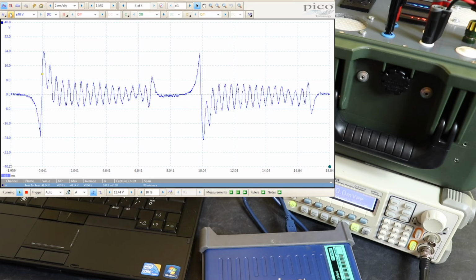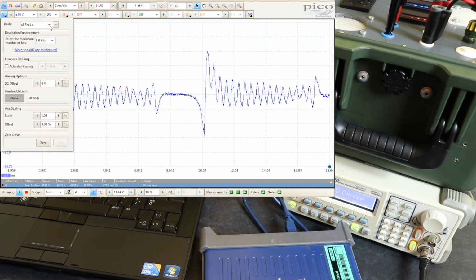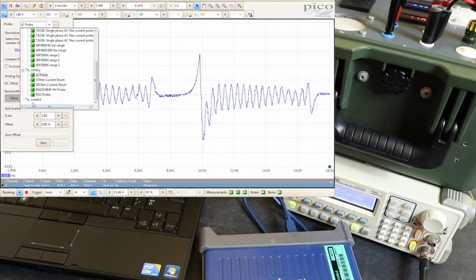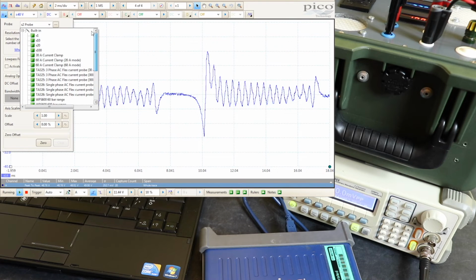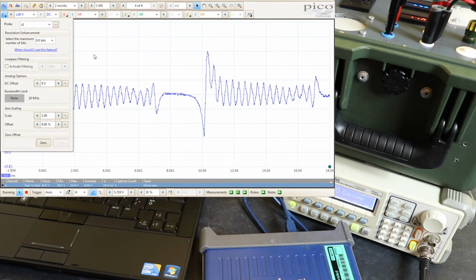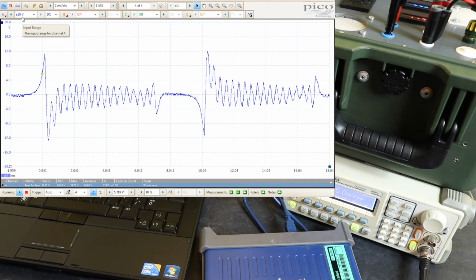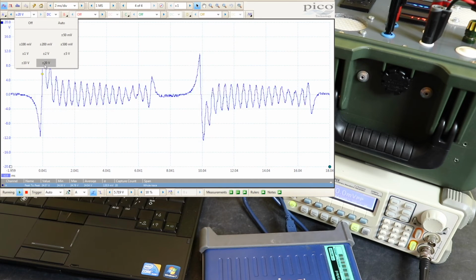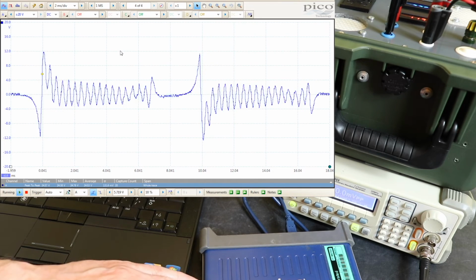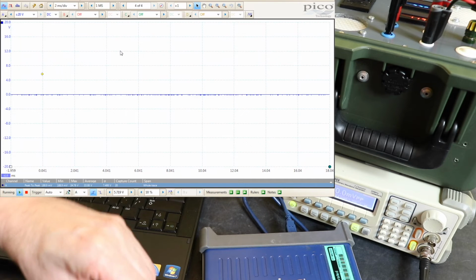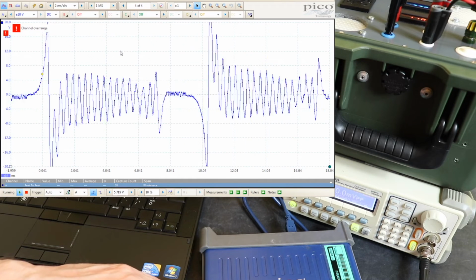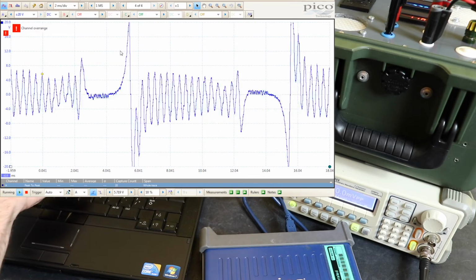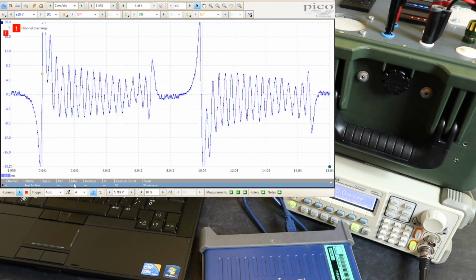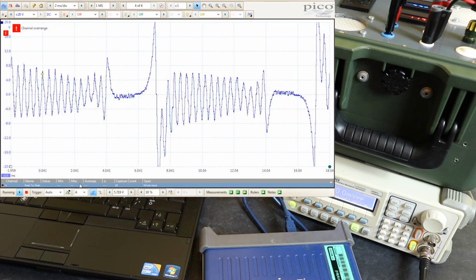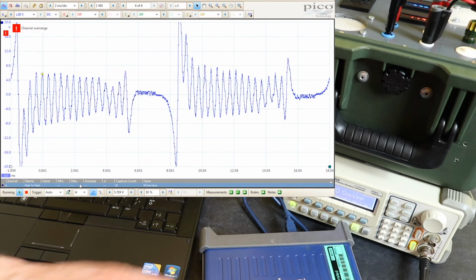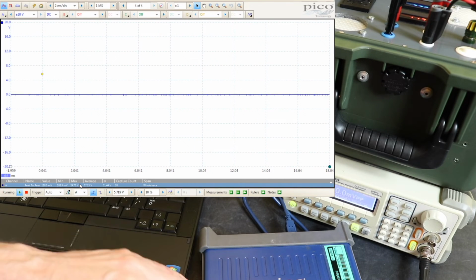I'll just show you very briefly what else I have to do. I've set this to a ×2 probe, so that's a probe that I've made up myself within the library. If I set this to ×1, you can see I now only get a 20 volts maximum on the signal. I lose that 40 volts, and if I just quickly drop the divider box off and put this on, you can see I end up with overrange and I don't get a maximum reading down here at the bottom, or the average either, for the peak to peak. So that's why I need the actual voltage divider to enable me to get this to work.